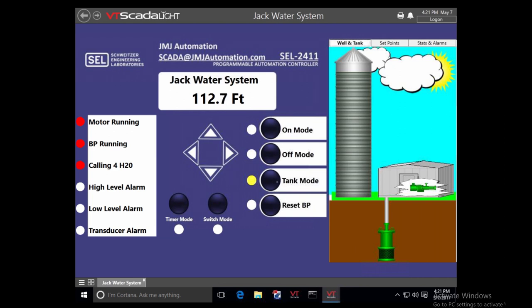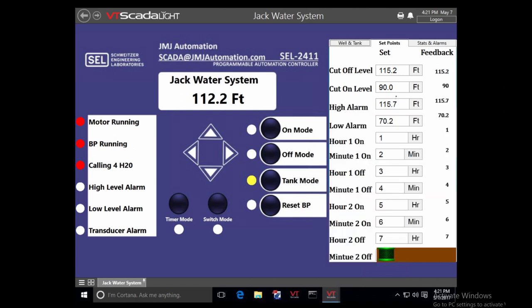And in tank mode, you have set points. You can set the set points to whatever cut-on and cut-off levels you want. You can alarm on high-level alarm, low-level alarm. In timer mode, you can tell what time you want it to turn on and what time you want it to turn off.